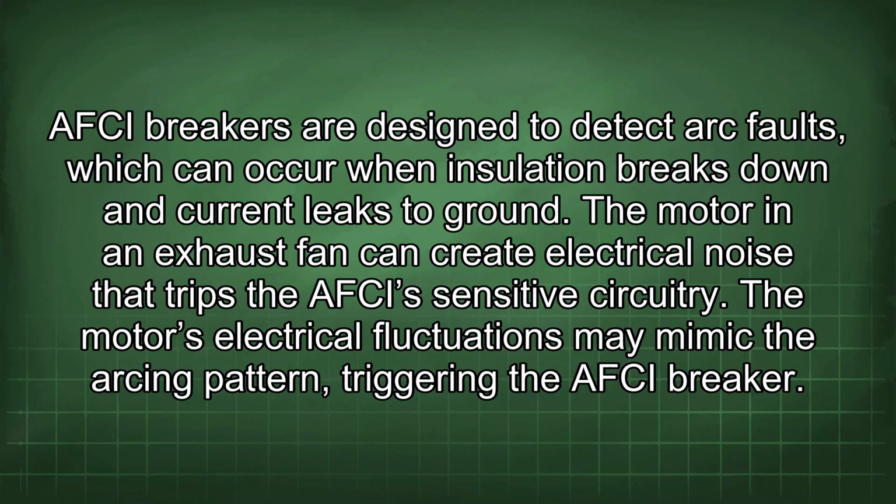AFCI breakers are designed to detect arc faults, which can occur when insulation breaks down and current leaks to ground. The motor in an exhaust fan can create electrical noise that trips the AFCI's sensitive circuitry. The motor's electrical fluctuations may mimic the arcing pattern, triggering the AFCI breaker.